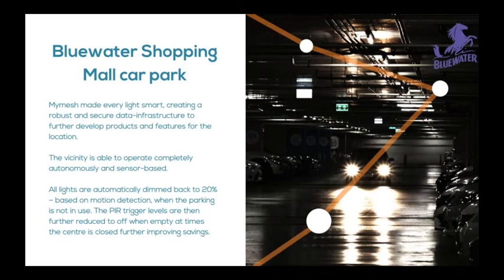So they asked us, could we do something that would enable the lighting to still function but change the set point. So we reprogrammed the entire system remotely and changed the unoccupied level to 0 and the occupied level to 50%. So as soon as somebody walked in there, for a security walk around, the lights came on, and then they went back to 0.